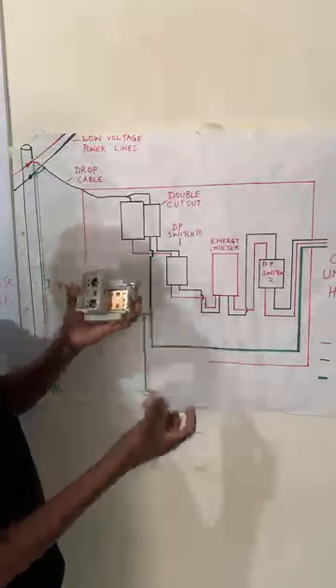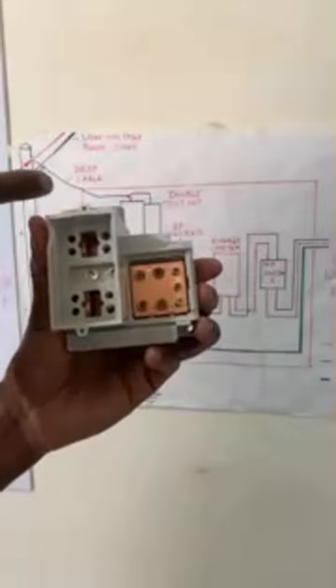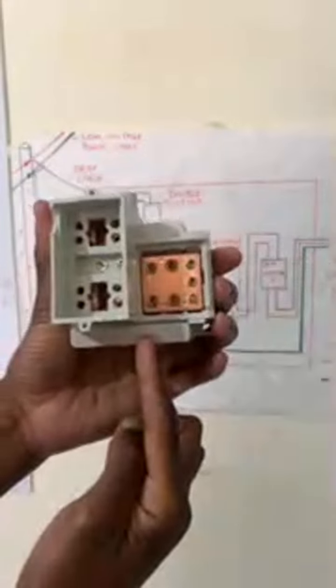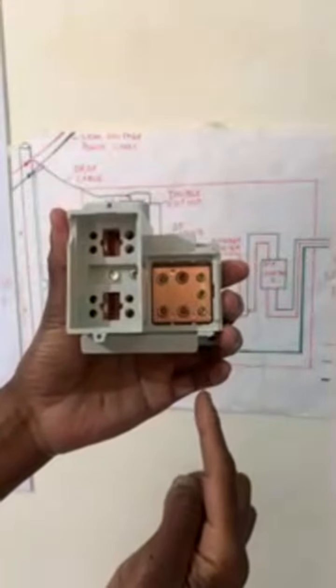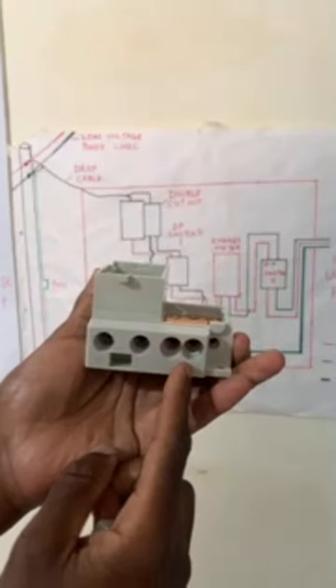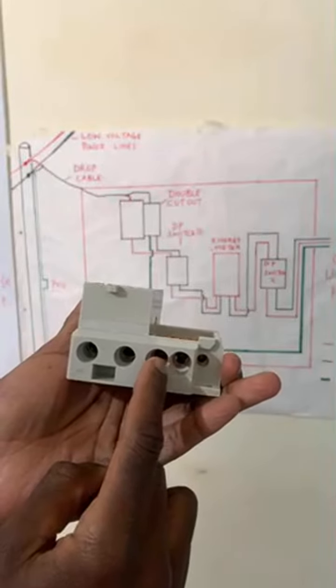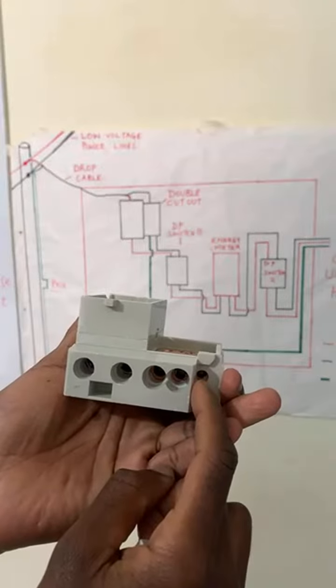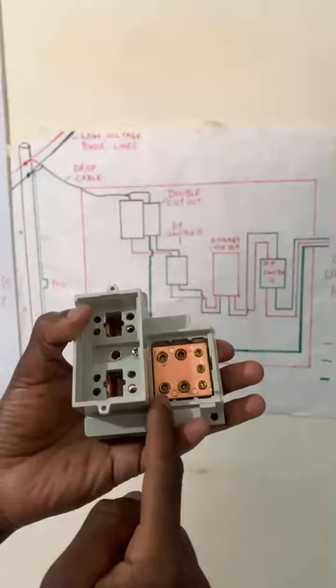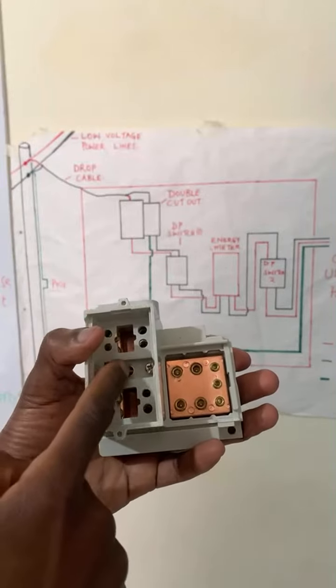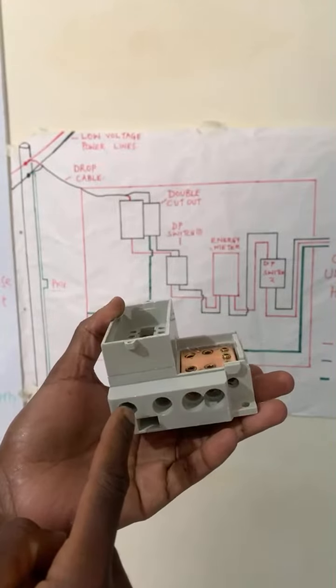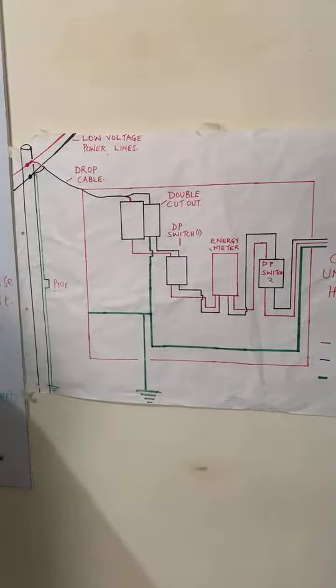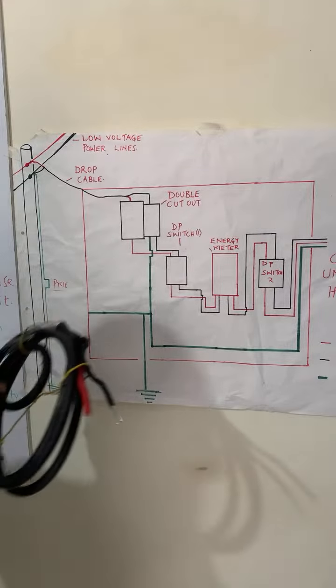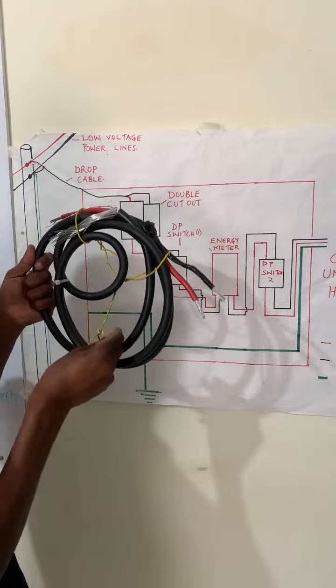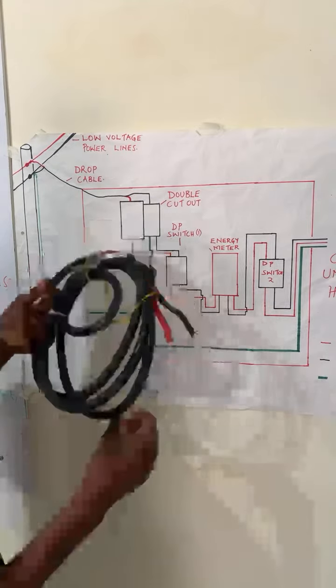So at this point where we will have the neutral connection, there is this plate here that is of importance to us to take note. So once the phase drops here, the neutral drops here. At this point here is where we will tap our neutral, and we will tap our earth connection from this point down here. So if the neutral is connected there, the earth connection is connected here. We can have two neutral points connected here and an earth connection connected at this point. So that is how we will be bonding. The phase remains constant, where the incoming phase gets all the way through the fuse and exits at this point. All right. So that connection is usually done through what we refer to as a drop cable. So this is our drop cable that we are using.